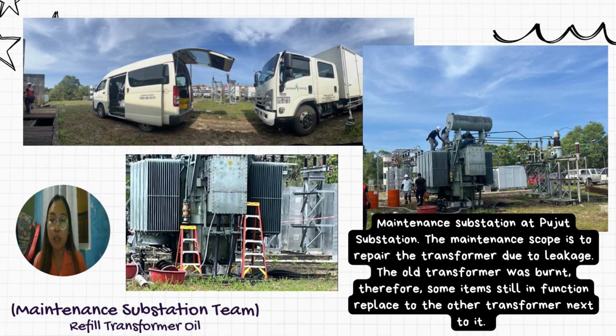This is when I'm joining the maintenance substation team, which is refilling the transformer oil. The maintenance substation at Pujut Substation, where the maintenance scope is to repair the transformer due to leakage. The old transformer was burned, so there are some items that are still functioning transferred to the new transformer for it to resume operations. And also, due to the leakage, the spare tank transformer lacks oil. So at the same time, the maintenance substation team refills the oil.